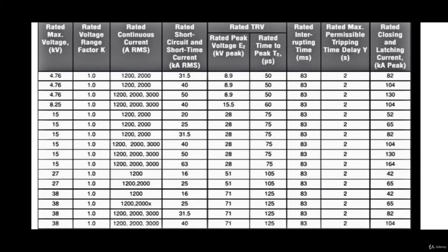According to that SCCR value, you have to check or select your component. Consider your component has to withstand a 40k short circuit current value, or 40k RMS. According to that you will select your component. So you don't have to calculate again for your SCCR with your component. You are directly going to get the SCCR from your components.